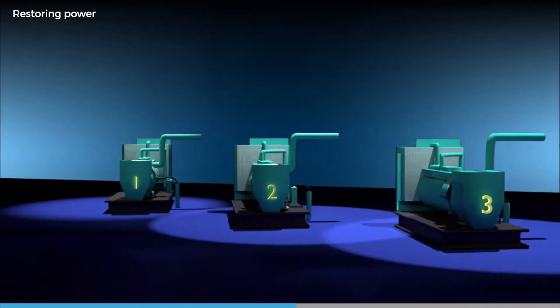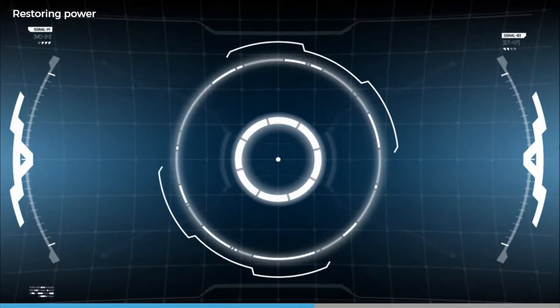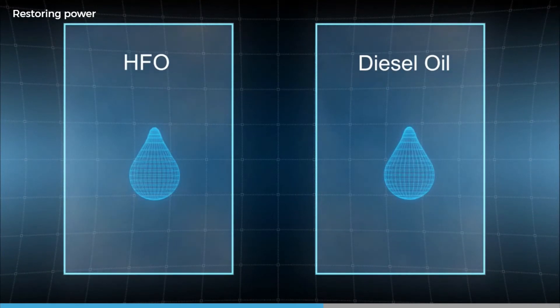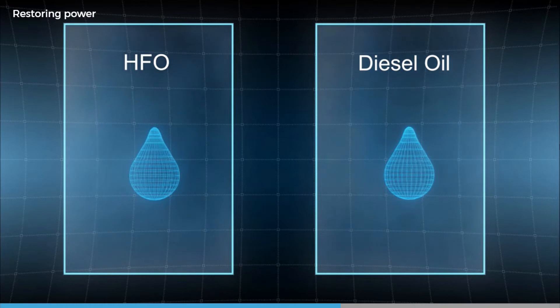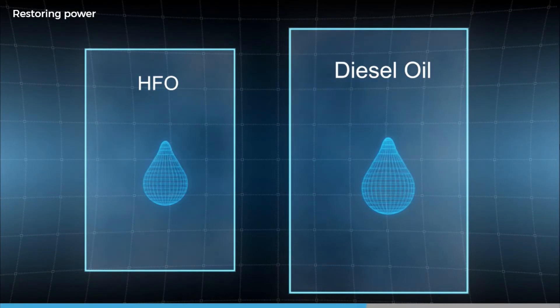So, know which main generator can be started in a blackout and how to do this. Consider if you can still start them on heavy fuel oil, because you may or may not have enough residual heat and steam to do this. Change over to distillate fuel if in doubt.